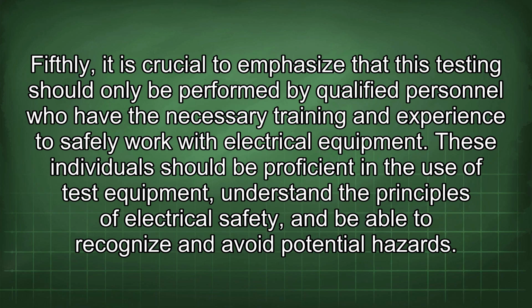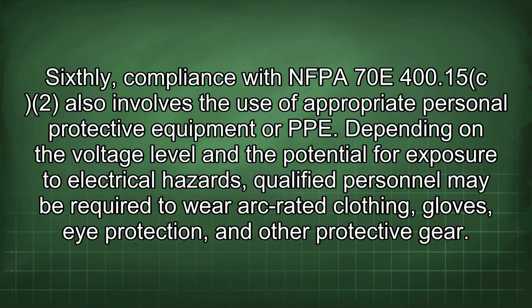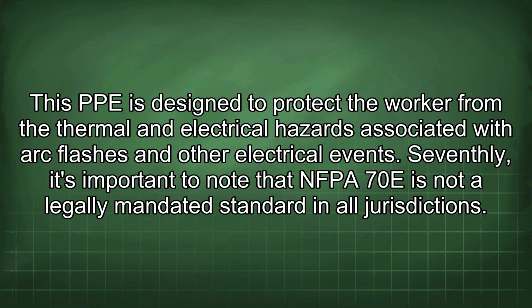Fifthly, it is crucial to emphasize that this testing should only be performed by qualified personnel who have the necessary training and experience to safely work with electrical equipment. These individuals should be proficient in the use of test equipment, understand the principles of electrical safety, and be able to recognize and avoid potential hazards. Sixthly, compliance with NFPA 70E 400.15 also involves the use of appropriate personal protective equipment or PPE. Depending on the voltage level and the potential for exposure to electrical hazards, qualified personnel may be required to wear arc-rated clothing, gloves, eye protection, and other protective gear. This PPE is designed to protect the worker from the thermal and electrical hazards associated with arc flashes and other electrical events.